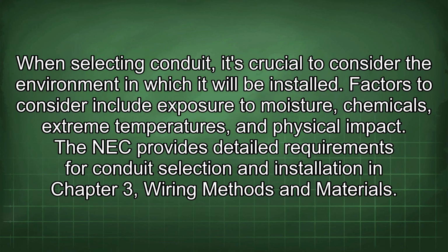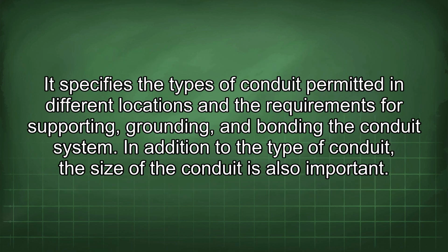When selecting conduit, it's crucial to consider the environment in which it will be installed. Factors to consider include exposure to moisture, chemicals, extreme temperatures, and physical impact. The NEC provides detailed requirements for conduit selection and installation in Chapter 3, Wiring Methods and Materials. It specifies the types of conduit permitted in different locations and the requirements for supporting, grounding, and bonding the conduit system.